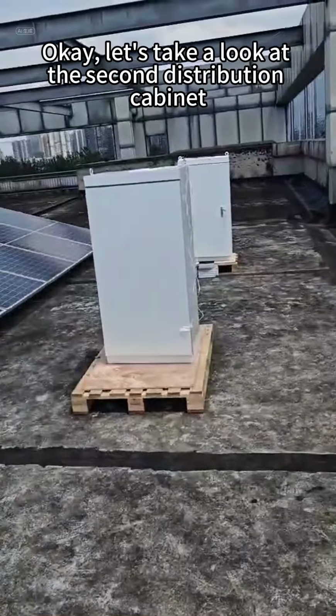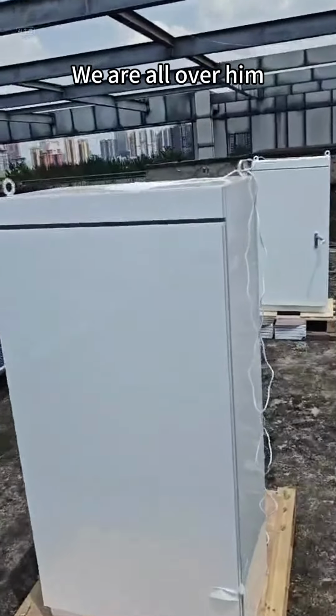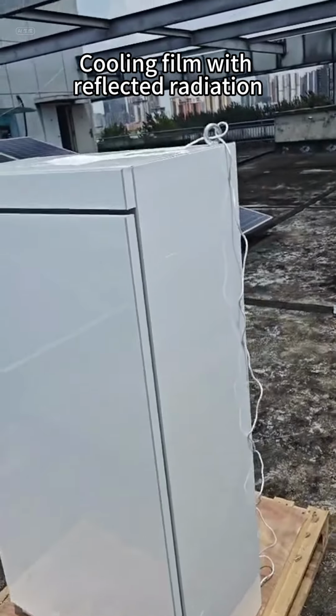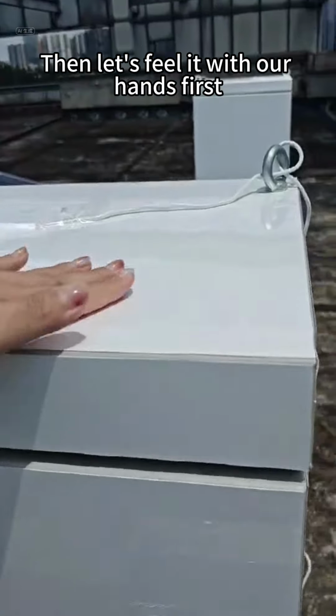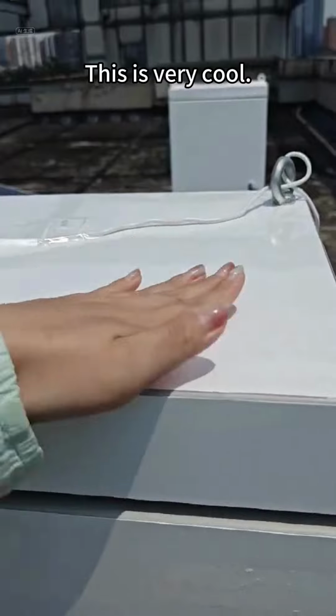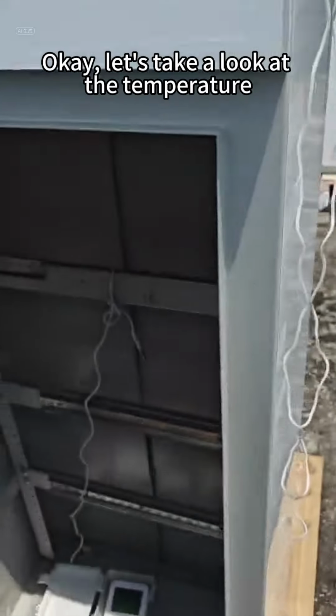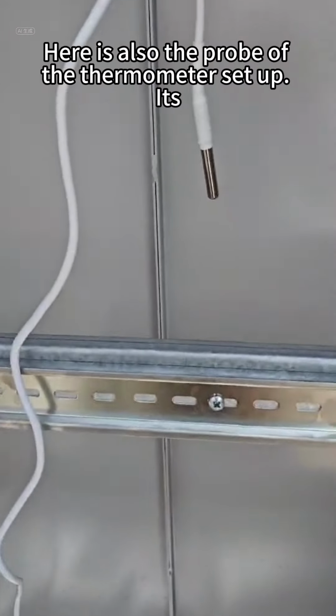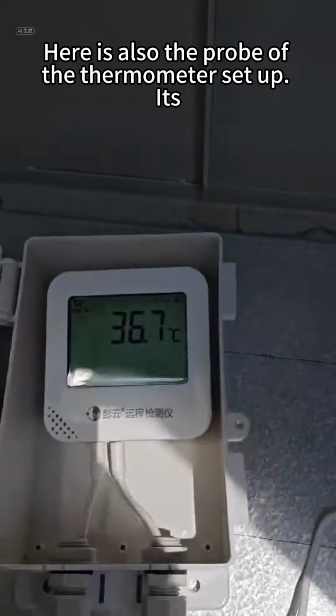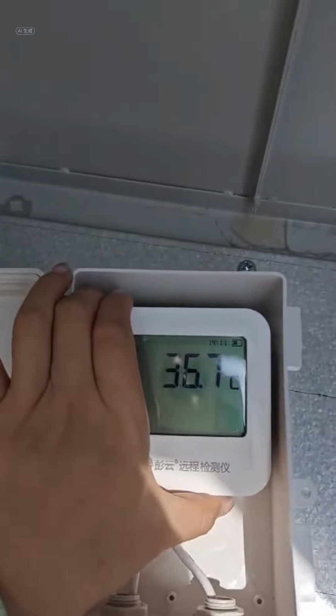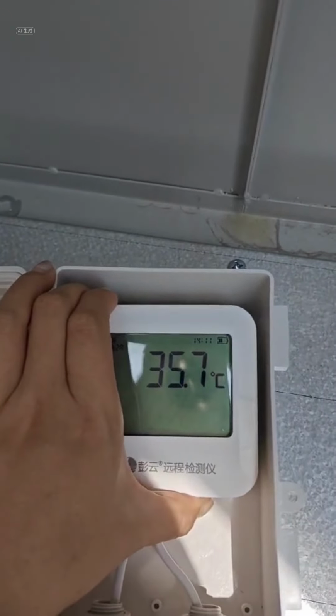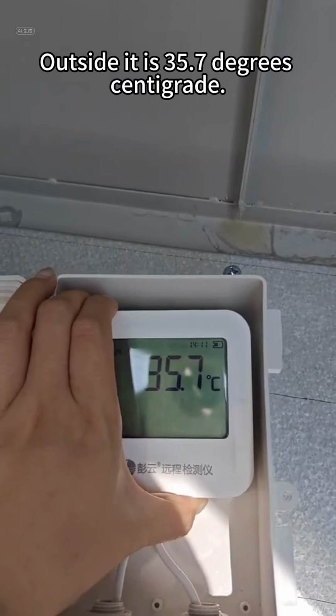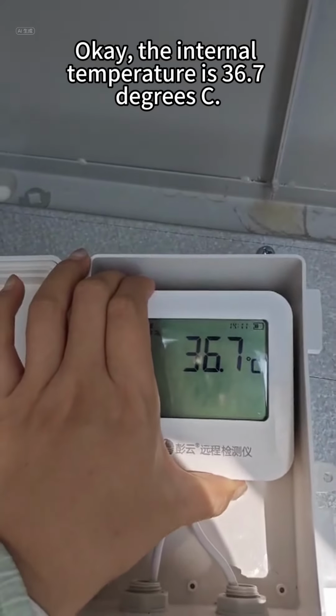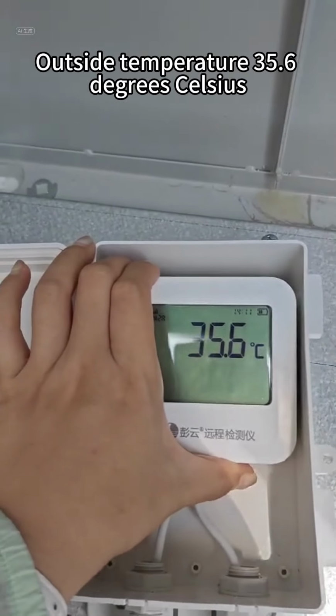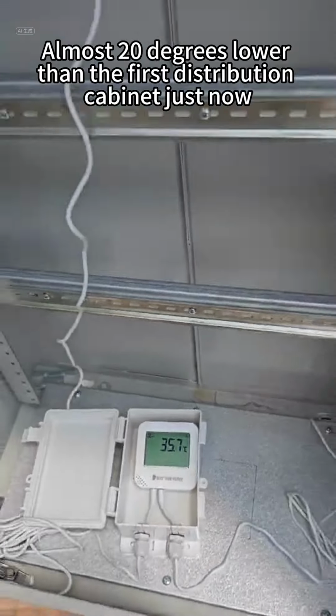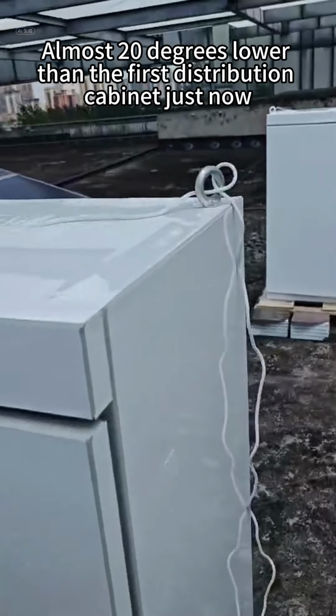Okay, let's take a look at the second power distribution cabinet. In the second distribution cabinet, we pasted a cooling film that reflects radiation on his whole body. Then we first feel it with our hands. This is very cool. Okay, let's take a look at the temperature. The probe of the thermometer is also set here. The internal temperature is 36.7 degrees C. The outside temperature is 35.6 degrees centigrade. It was nearly 20 degrees lower than the first distribution cabinet just now.